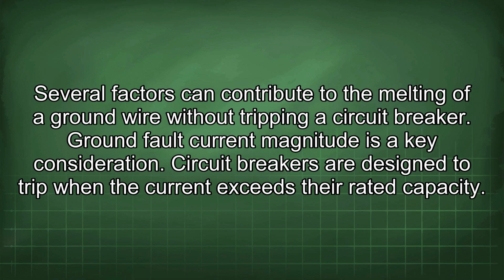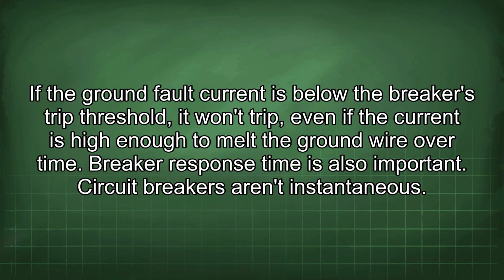Several factors can contribute to the melting of a ground wire without tripping a circuit breaker. Ground fault current magnitude is a key consideration. Circuit breakers are designed to trip when the current exceeds their rated capacity. If the ground fault current is below the breaker's trip threshold, it won't trip, even if the current is high enough to melt the ground wire over time. Breaker response time is also important.